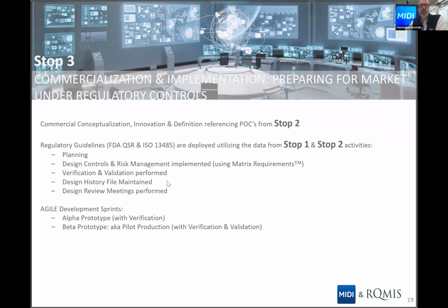Again, we use a tool called Matrix Requirements. It's in the cloud. Planning, and in your design controls, accommodating for the verification and validation and the traceability of that with each of your requirements and design inputs. And building out that design history file and maintaining it, and making sure you have preemptive design review meetings and performing those. We do this in an agile development sprint fashion. So with the alpha prototypes, once they are created, we're verifying against the design control document. And for the beta prototypes, which are really AKA pilot production off tooling, we're doing verification and validation, field validation, all traced back to the design control document.